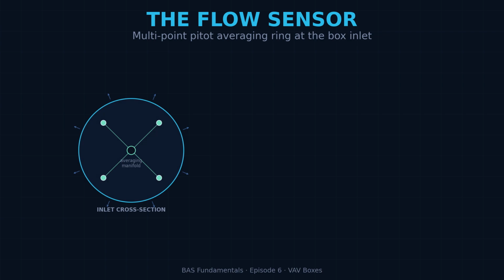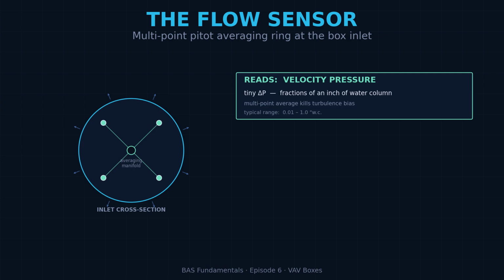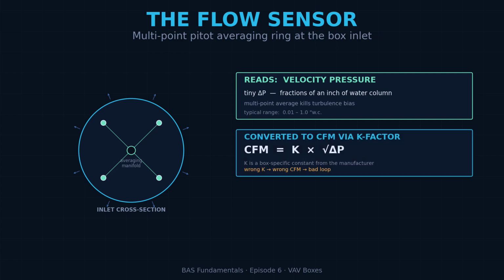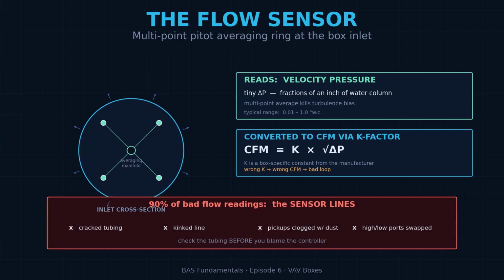The flow sensor is the piece everyone gets wrong. It's a multi-point pitot averaging ring at the inlet of the box. It reads the velocity pressure of the incoming air as a tiny differential pressure, usually fractions of an inch of water column. The controller converts that pressure into CFM using a K factor, which is a box-specific constant from the manufacturer. If your flow reading looks crazy, 90% of the time it's the sensor lines. Cracked tubing, kinked line, pickups clogged with construction dust, or the lines swapped between high and low ports. Always check the tubing before you blame the controller.